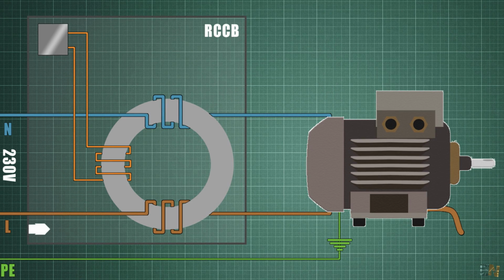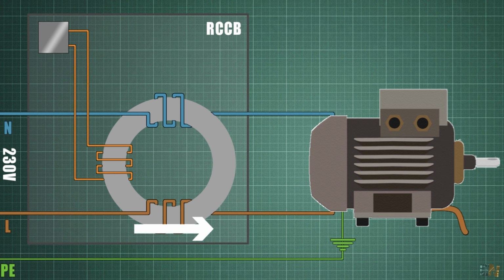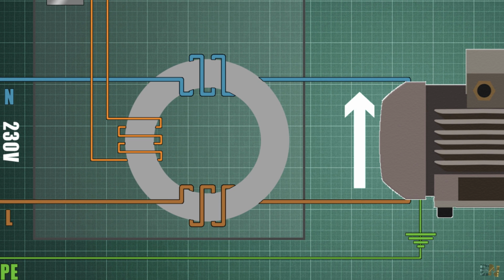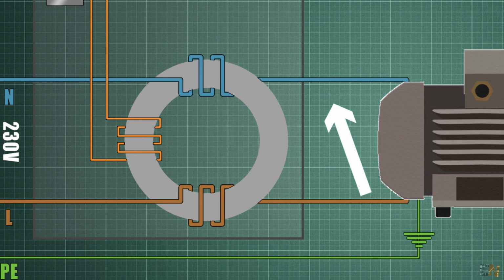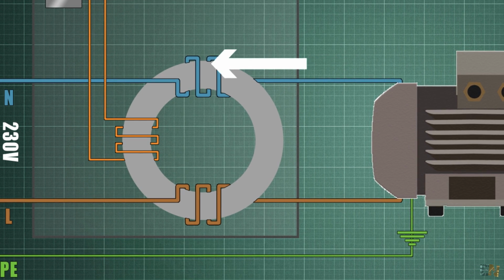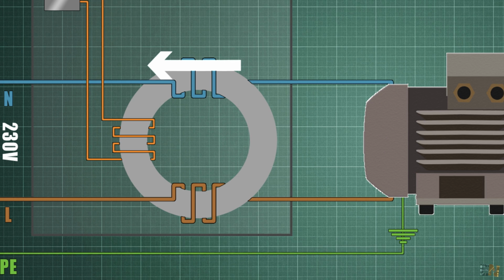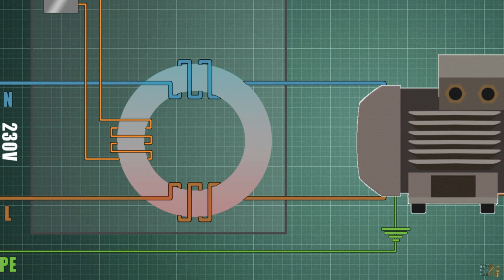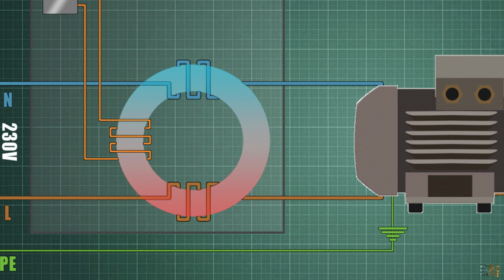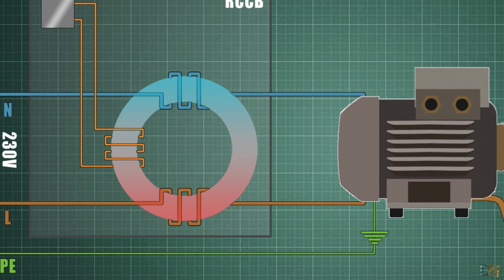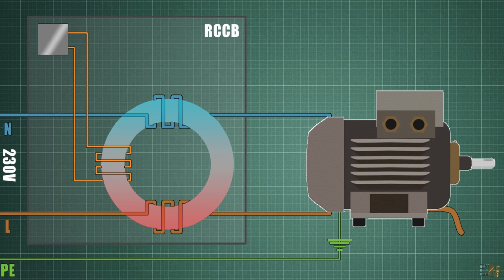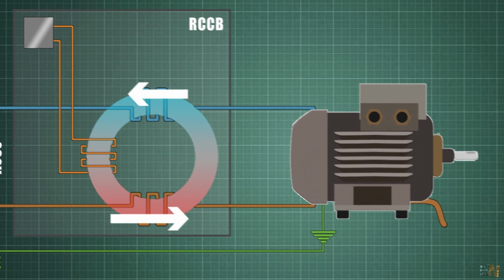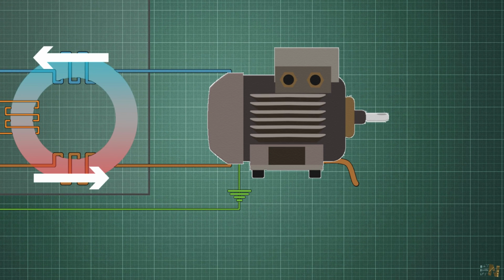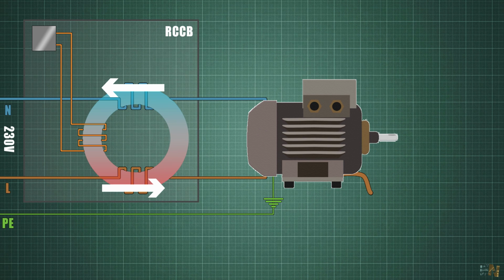Now current is flowing from the L1 through one side of the transformer and then it passes the load. That same current value is now flowing back to neutral and at the same time is passing back through the other side of the transformer. We know that this current will create magnetic fields inside of the core of the transformer. But since we have the same amount of current that is going through the transformer in this way and in this way, the magnetic fields are opposed and in equal value. So that means that the field is in equilibrium and the magnetic inductions will cancel each other out.